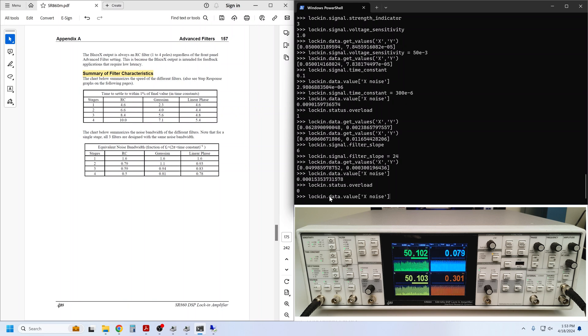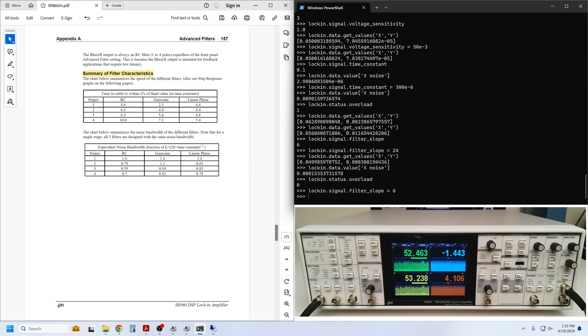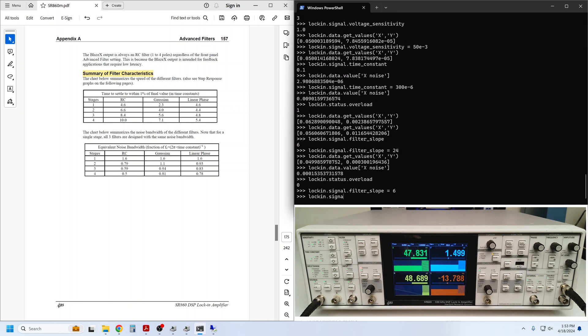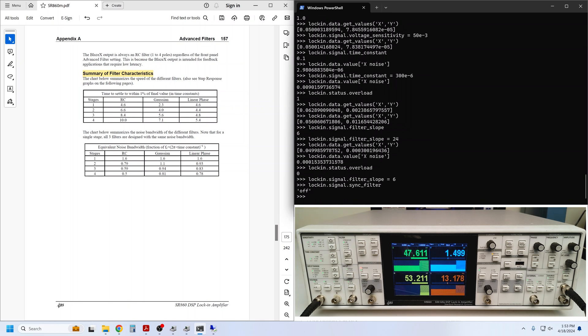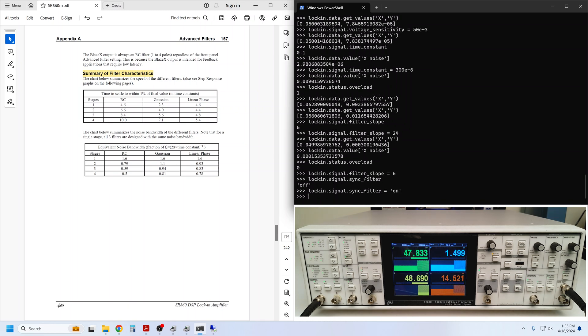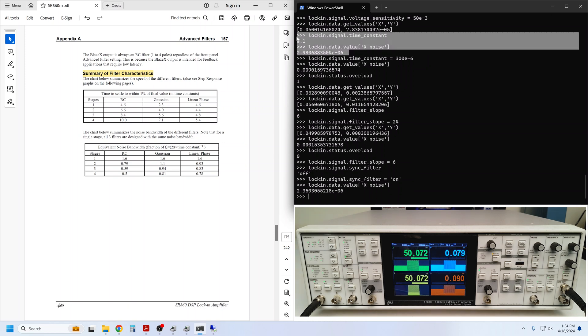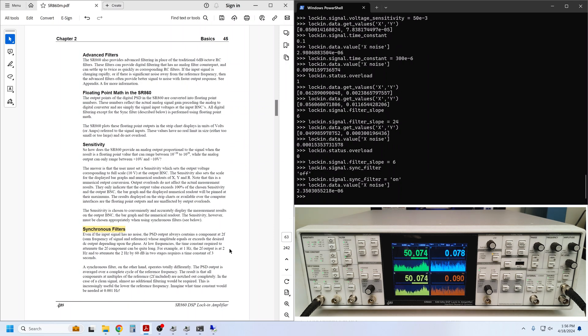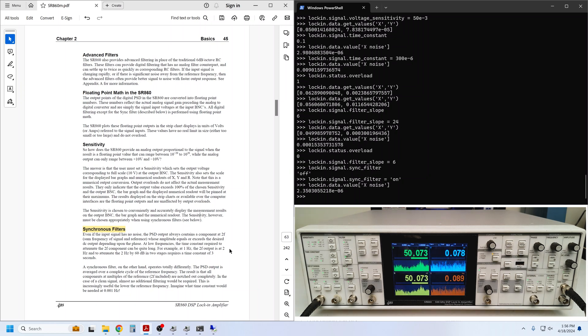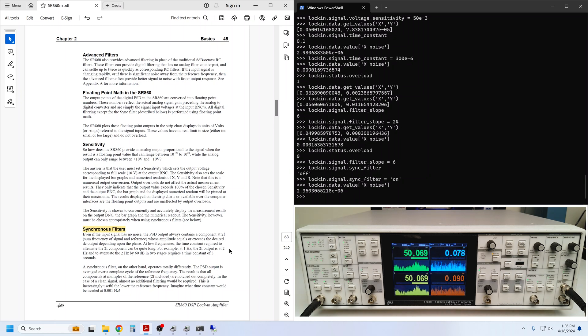Even if we leave the filter at 6 dB per octave, we can reduce the noise dramatically by enabling synchronous filtering. By default, this is set to off, so I'll go ahead and turn it on. We can ask about X noise again, and see that it is reduced to a level that previously required the 100 millisecond time constant, comparing to the value here. The sync filter averages the multiplier's output over one full cycle of the reference frequency. The integral of a sine wave over its period is 0, so all signals at F, 2F, and higher multiples are eliminated by this averaging.